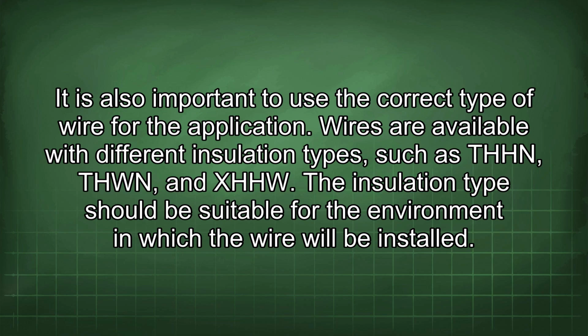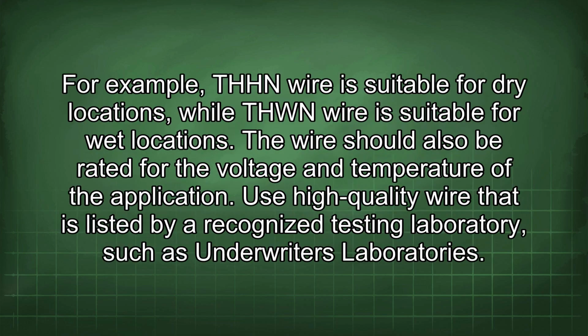It is also important to use the correct type of wire for the application. Wires are available with different insulation types, such as THHN, THWN, and XHHW. The insulation type should be suitable for the environment in which the wire will be installed. For example, THHN wire is suitable for dry locations, while THWN wire is suitable for wet locations. The wire should also be rated for the voltage and temperature of the application. Use high-quality wire that is listed by a recognized testing laboratory, such as Underwriters Laboratories.